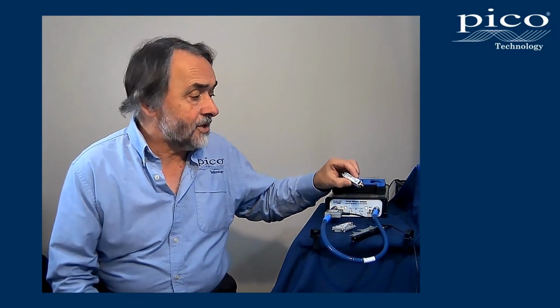So next we'll check out the quality of the calibration using our PicoVNA check standard. This is a mismatched 25 ohm line between the two 50 ohm SMA connectors there, a precision stable mismatched line, and this makes a very good, very comprehensive check of our VNA calibration, because this has to be measured very accurately in the presence of its own very substantial mismatch, and so this is a very good test as to whether the ports of the VNA have been calibrated well.